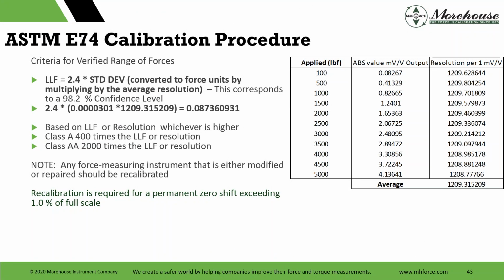So, calibration procedure, criteria for verified range of forces: the lower limit factor is 2.4 times the standard deviation converted to force units, multiplied by the average resolution. Here we're doing that right now. People are probably saying, hey, what's this? When is it going to talk about this? So here's the math, 2.4 times this. We're going to take 0.0000301, multiply it by 1209. Remember, if we just did it by the capacity point, we would have been at 1208, slightly different, slightly lower. So we're going to multiply it by the average of all of them. And that corresponds to what we get, a lower limit factor of 0.08736.